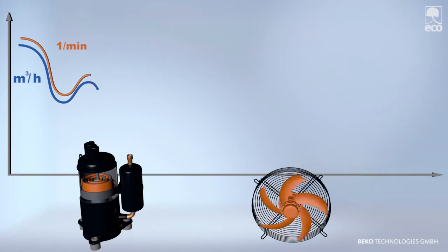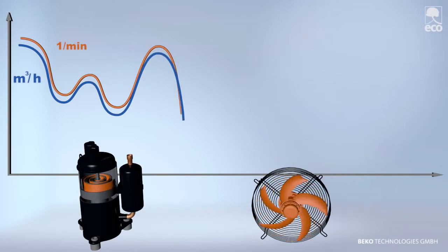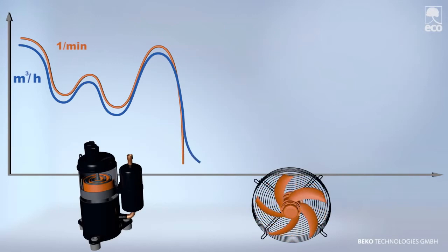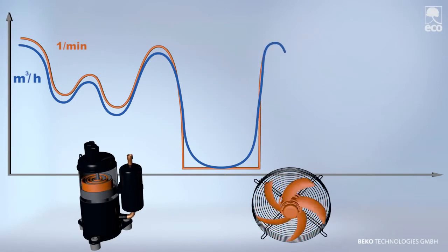smaller versions of the dry point RA Eco switch the refrigerant compressor on and off to accommodate variations in the drying requirements. After reaching a certain system size, the drying performance is controlled by changing the frequency of the compressor and thus even more finely adjusted to the volume flow.